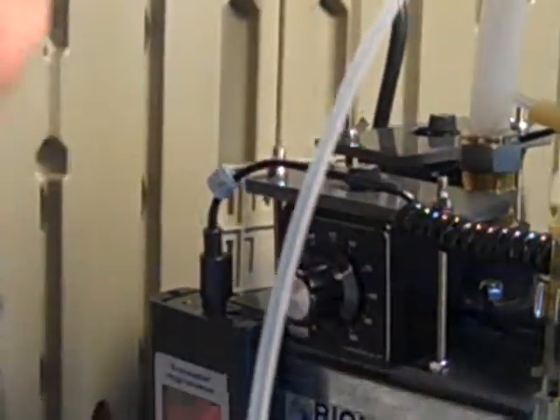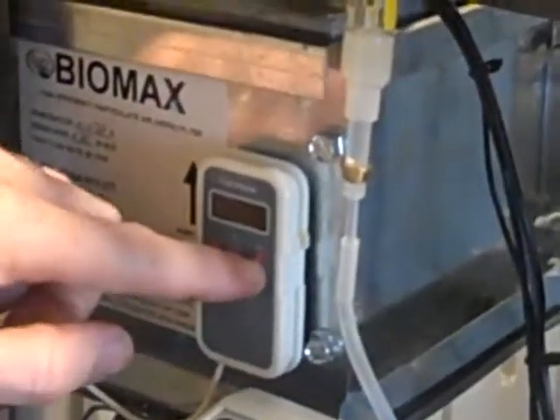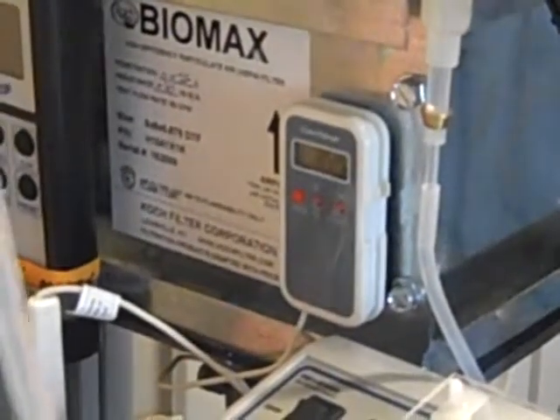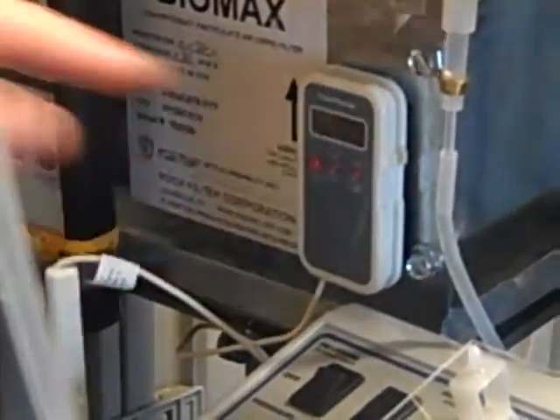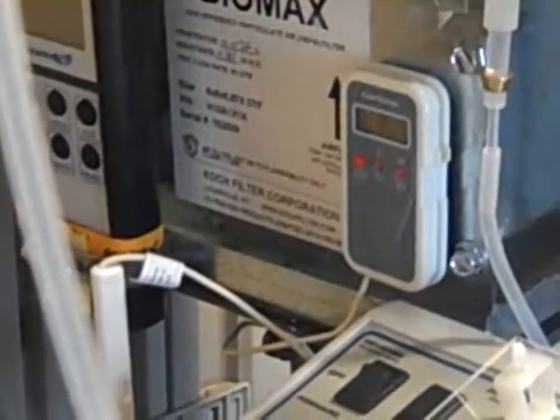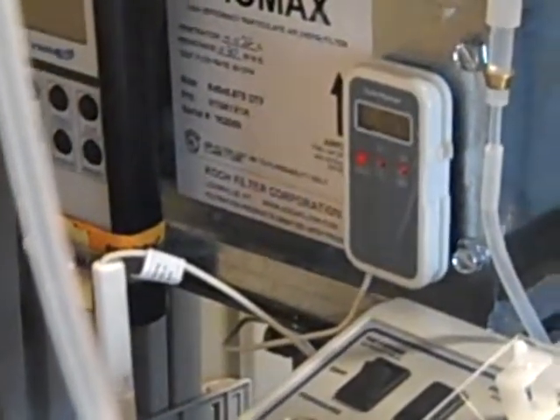The next thing we want to do is turn on the heaters for the humidifier, which are controlled by the rheostat in the back. You can't see it right now, but I'm going to set it at about 70. And I'm going to turn my temperature probe on. This is the air temperature probe. It measures the air temperature in the G2. And we're going to wait until that air temperature gets to about 120 degrees Fahrenheit before we turn on the second peristaltic pump that's going to humidify the system. So we'll let that go for now. And to turn on the RH meters, they have an auto off. You just hit the on button.